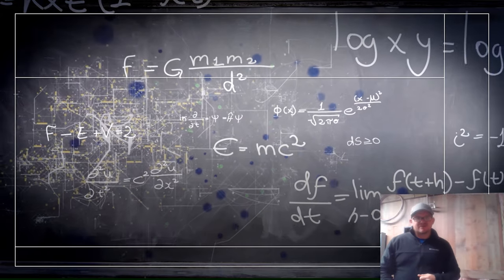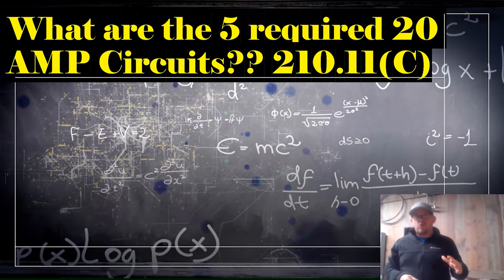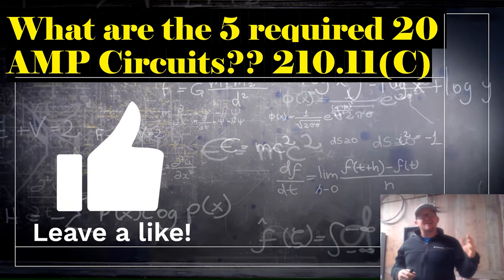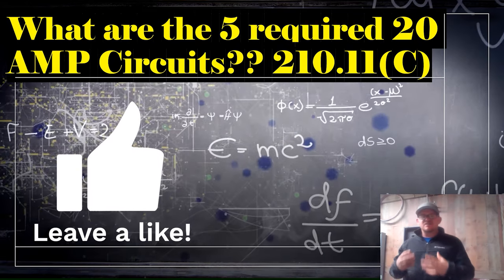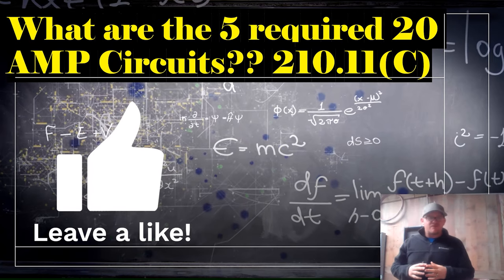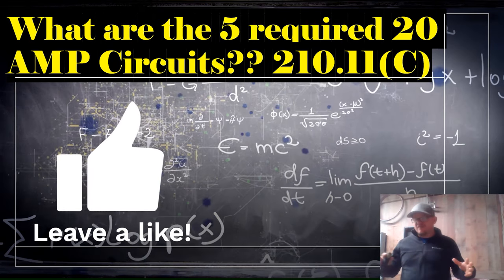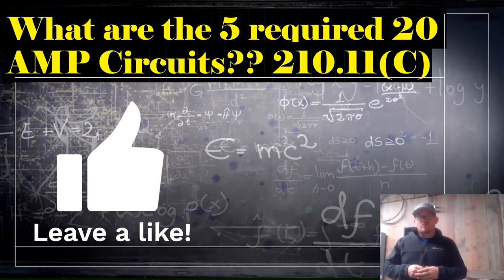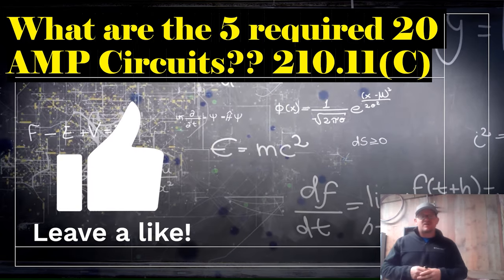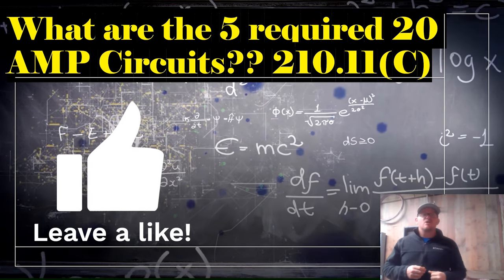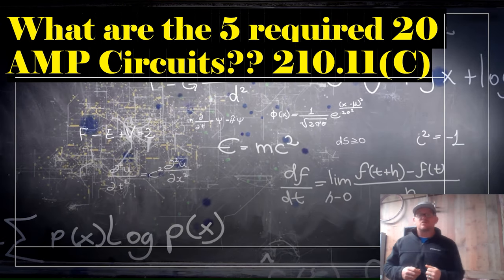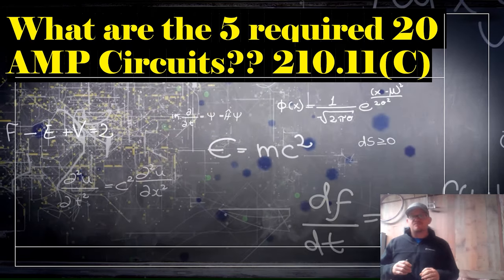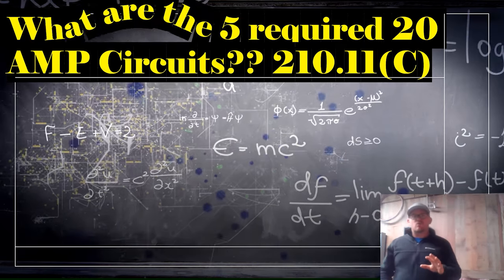Hey y'all, what's up — it's the Electrical Code Coach. Today we're going to talk about the five required 20-amp branch circuits. You can find this in Article 210.11(C). It doesn't matter if you want to run 14-gauge wire on a 15-amp breaker for all of your general lighting and receptacles in your whole home — these five required branch circuits are going to require 12-gauge wire.